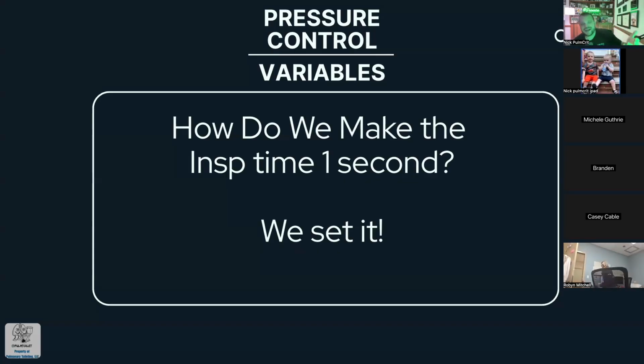Now it's easier to set an I time, personally, I think, with volume control, because you want it to be 1 second. Because before, if you saw the old Puritan Bennetts that had the big screens, you'd have to pick 30, 60, 90, 120 liters per minute of flow. And 30 meant that you have a very long inspiratory time because the flow is very small. 120 meant you had a very short inspiratory time because the flow was very high. But for pressure control, you're setting the I time.